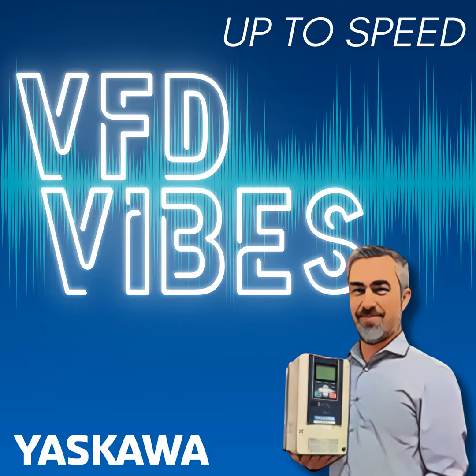When we talk about wasted power, something a lot of people overlook is vampire power. That's the electricity your drive still consumes when it's not even running. Like your TV that draws power in standby mode, VFDs can still pull current through the rectifier and capacitors even when idle. Some manufacturers, Yaskawa included, address this by offering features that use a small auxiliary DC supply to keep the brains of the drive alive while disconnecting the main power input. When a run command comes in, the drive wakes instantly without wasting idle energy in between.